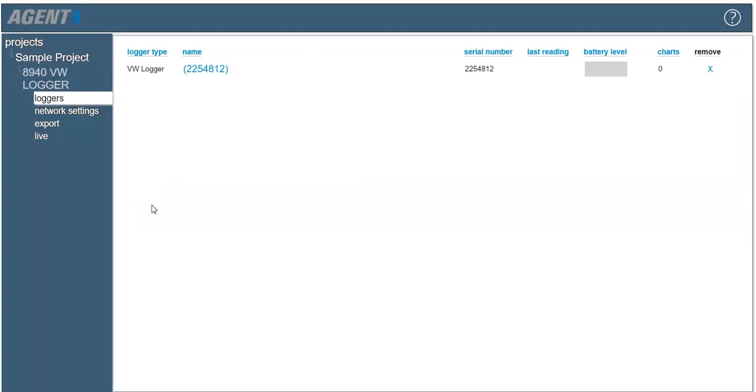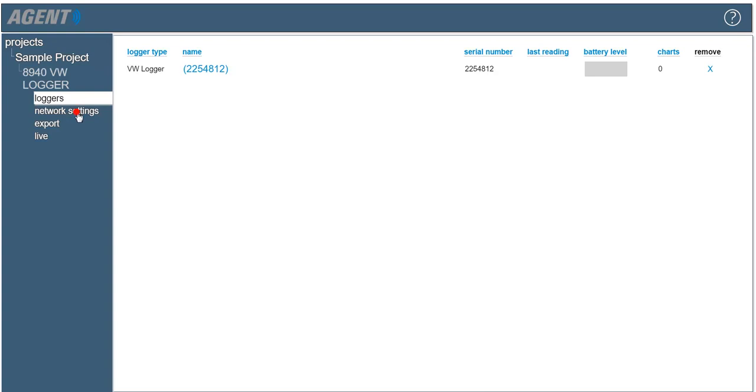Agent will automatically navigate to the logger screen. The last reading and battery level will populate once data has been downloaded from the logger. The current time must be sent to the data logger before it will begin taking readings. To set the time, navigate to the network settings screen, then click the set time button.